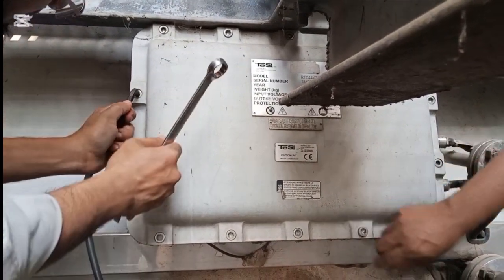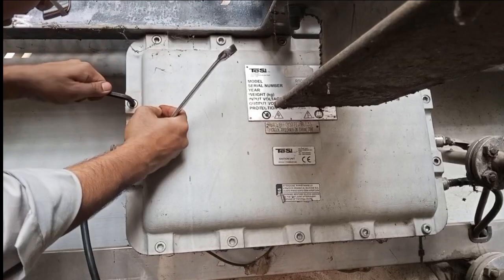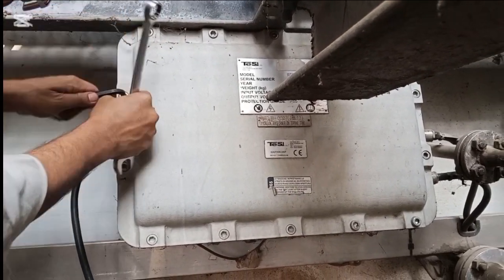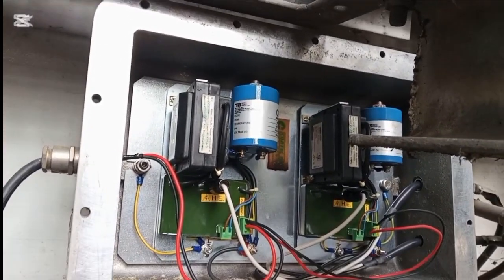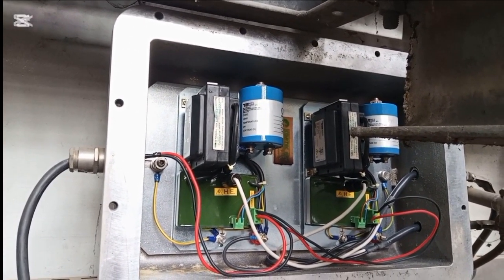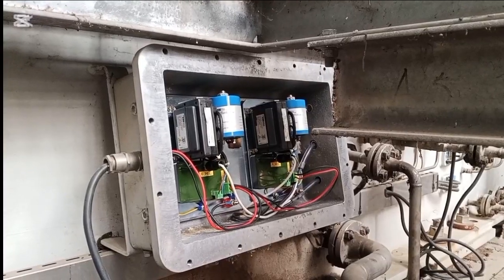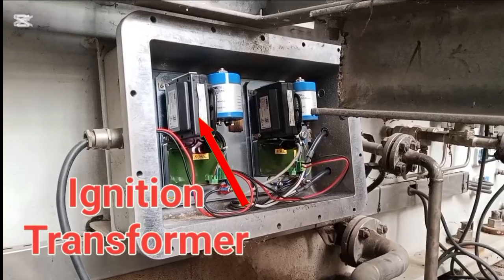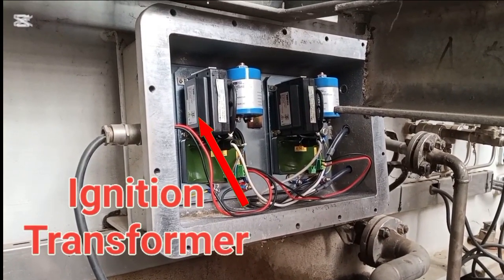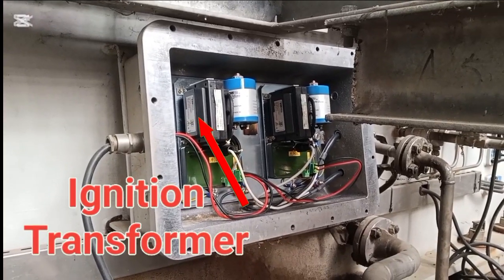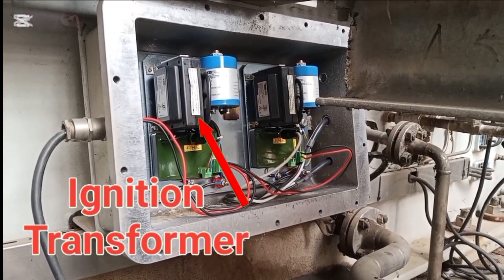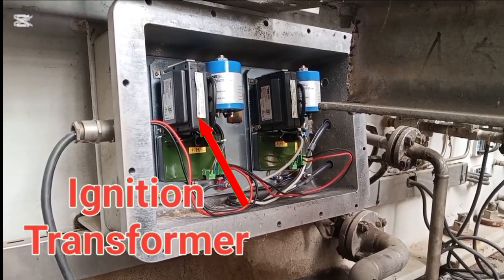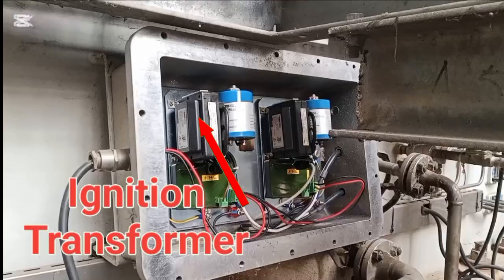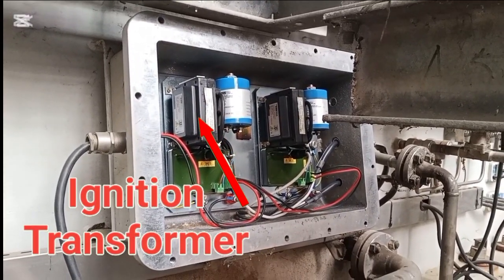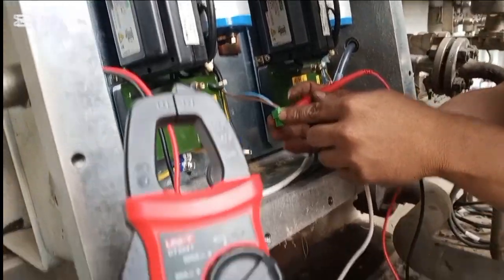This is the transformer box. From here, by cable connection, the transformer is connected with the spark plug electrode. Here we can see that the power supply is connected in parallel. At first it is connected with the control board, and then from the control board the transformer is connected with 230 volt AC, and its neutral is grounded. Here we can see the spark when the turbine is trying to ignite. We can see the two transformers.